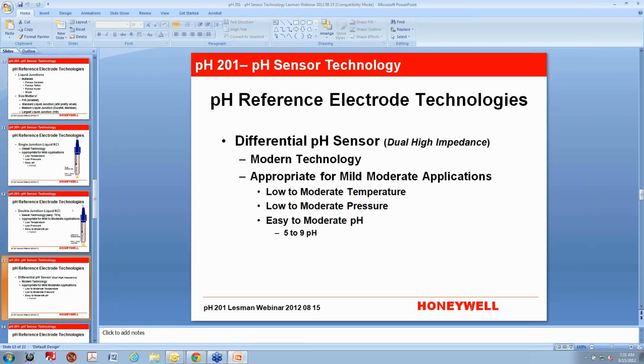I think they invented the differential pH sensor technology, and this was a step up from having a double or a triple junction with a liquid KCl inside. The way that works is you have your pH measuring electrode sticking out of the sensor just like normal, and then inside your sensor you have potassium chloride, and in the potassium chloride you have another tube. In the second tube is a buffer solution, and inside the buffer solution is a second pH sensor.